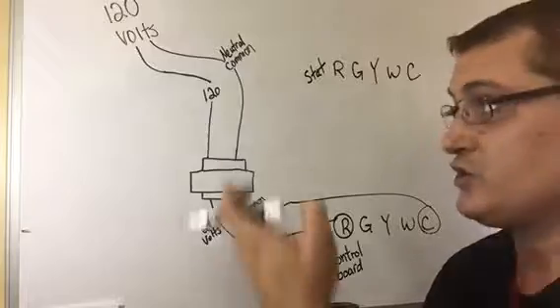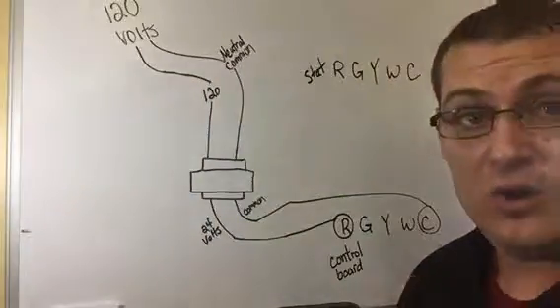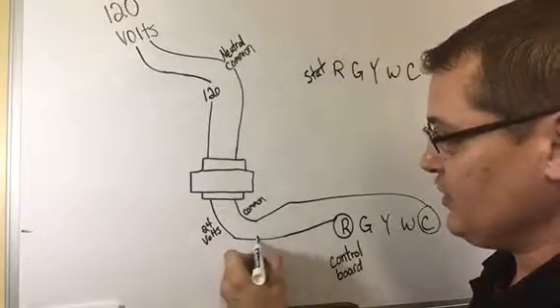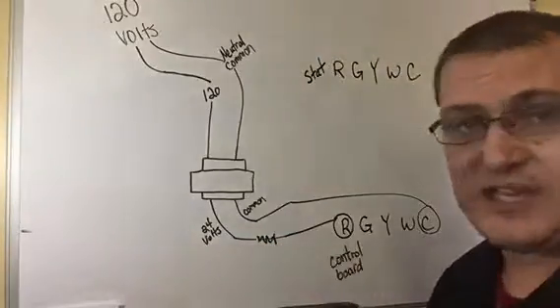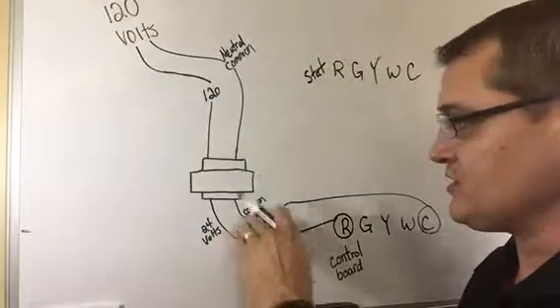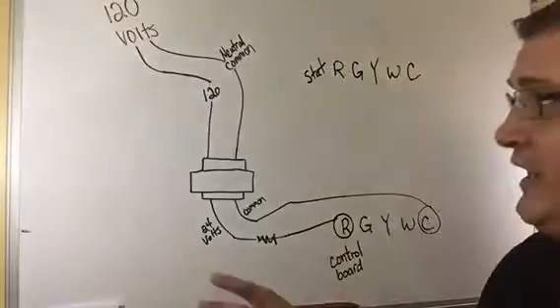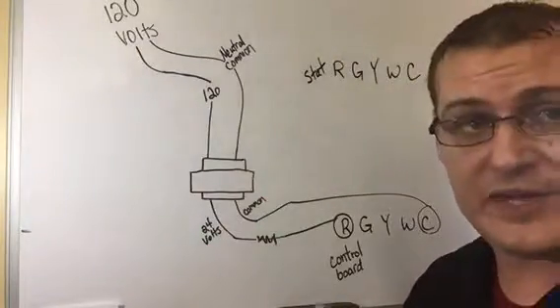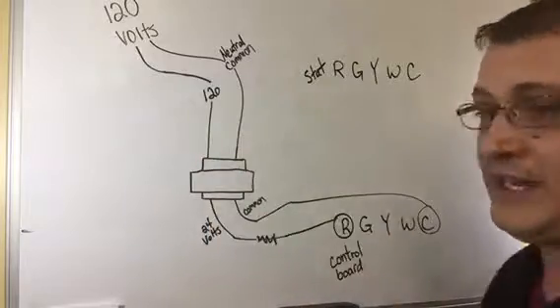If you didn't have 120 volt power, or if your transformer is bad, or sometimes they'll put a fuse in here, just in case there's a short it'll blow the fuse instead of blowing the transformer. But bottom line is, if everything is right and everything is good, you're going to read 24 volts.